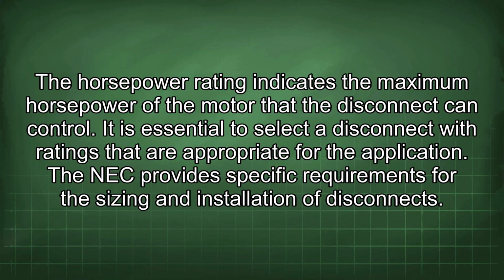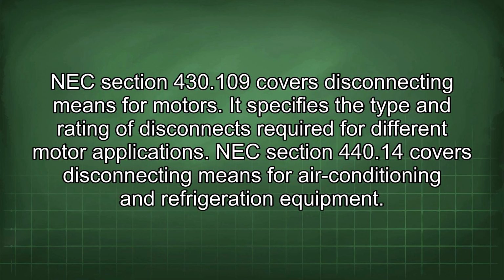The NEC provides specific requirements for the sizing and installation of disconnects. NEC Section 430.109 covers disconnecting means for motors. It specifies the type and rating of disconnects required for different motor applications. NEC Section 440.14 covers disconnecting means for air conditioning and refrigeration equipment.